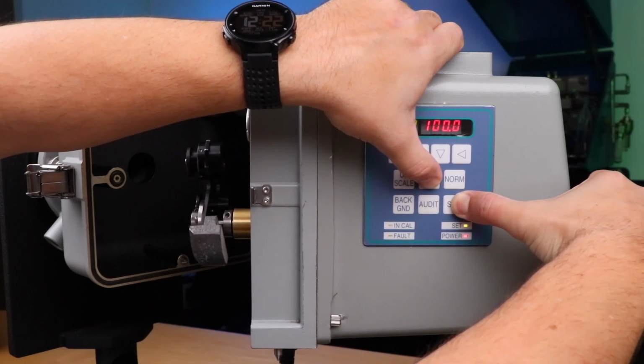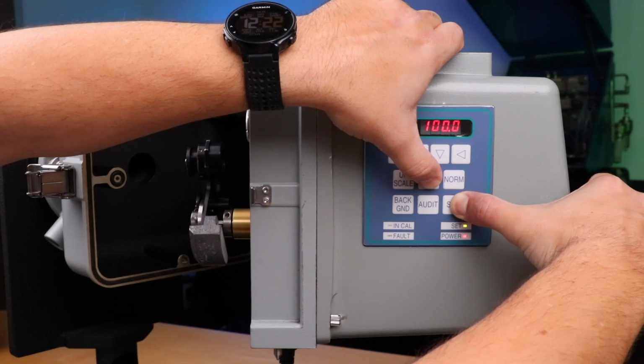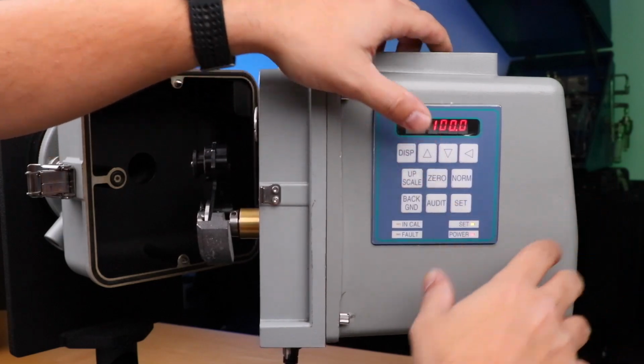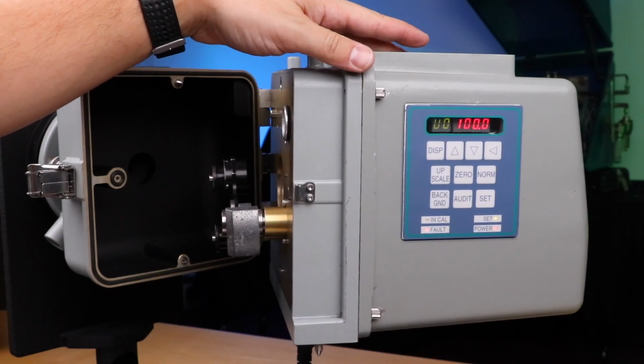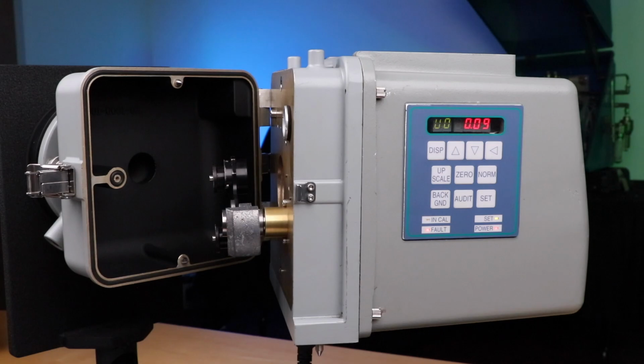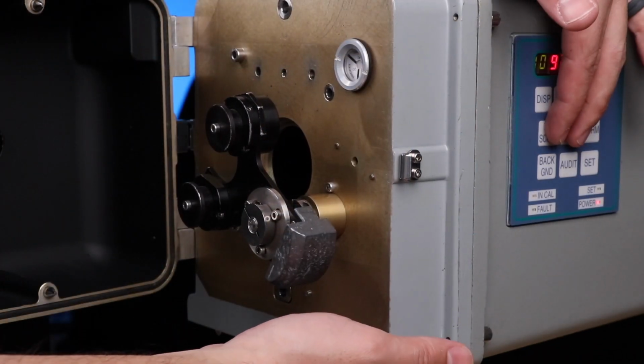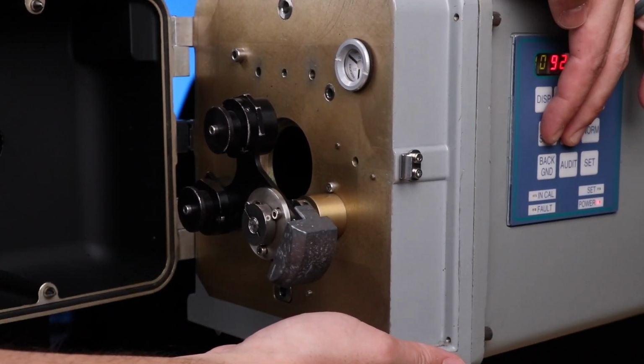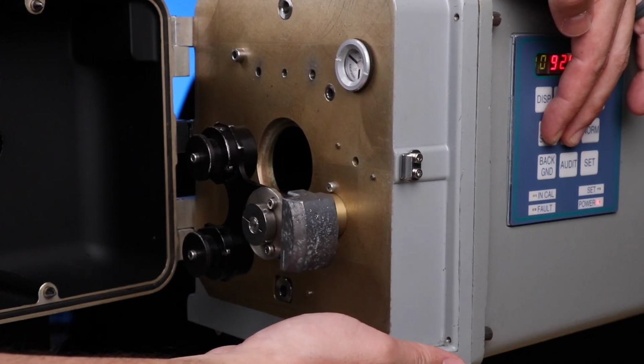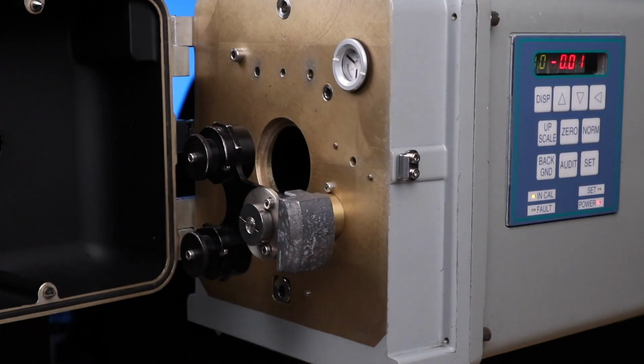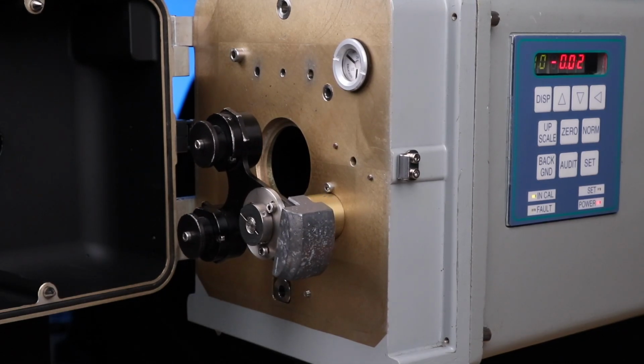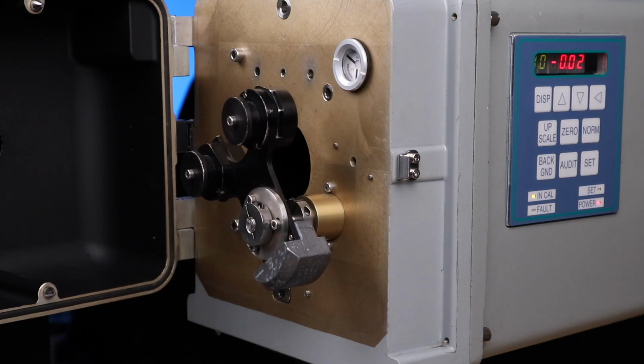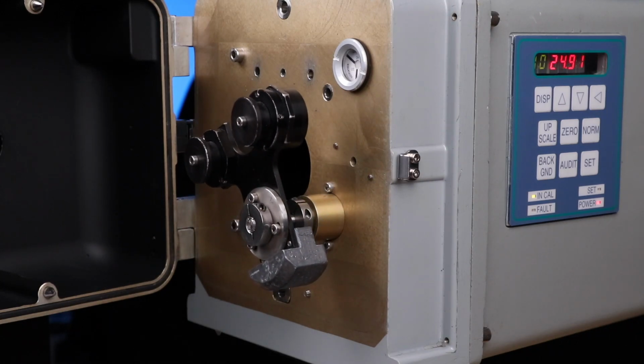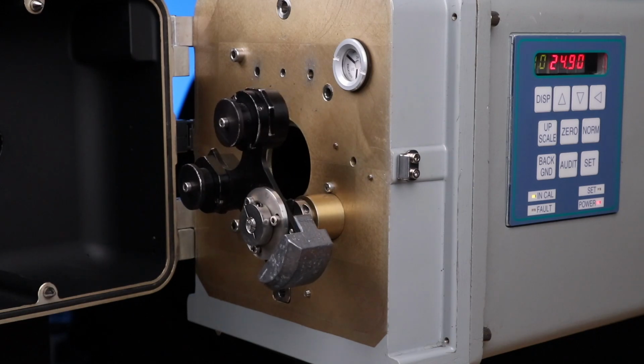Once the zero set is complete, the unit requires 2 calibrations to calculate drift. This would normally be done with the unit returned to normal, but we are leaving the unit open to show the cal mechanism. Initiate the cal by pressing Upscale and Zero buttons together, then letting go. Watch for the In Cal button to illuminate. The cal takes approximately 4 minutes. Notice the calibration mechanism lowers to check the zero, rises to check the span, and then returns to normal position once the check is complete.